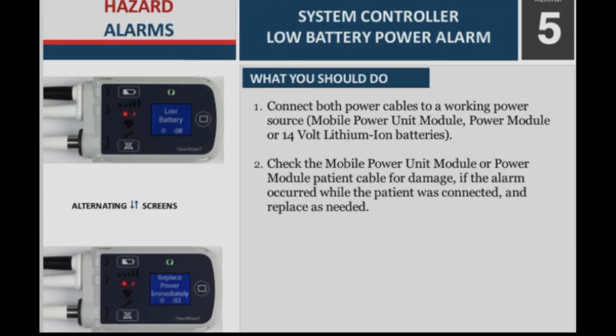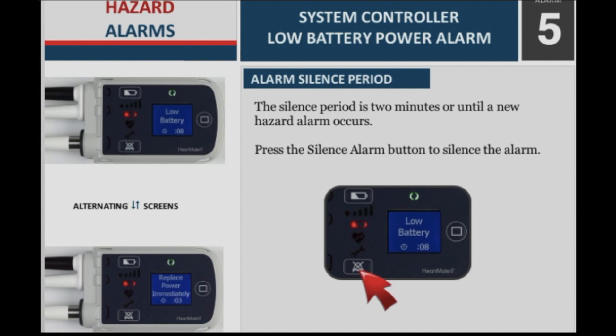What you should do: Step 1 — Connect both power cables to a working power source: mobile power unit module, power module, or 14V lithium ion batteries. Step 2 — Check the mobile power unit module or power module patient cable for damage, if the alarm occurred while the patient was connected, and replace as needed. Alarm silence period: The silence period is 2 minutes or until a new hazard alarm occurs. Press the silence alarm button to silence the alarm.